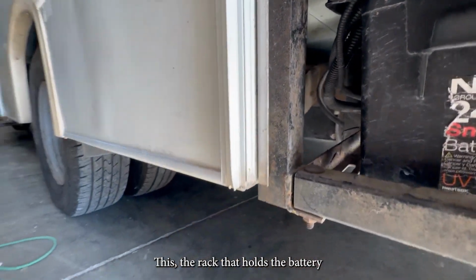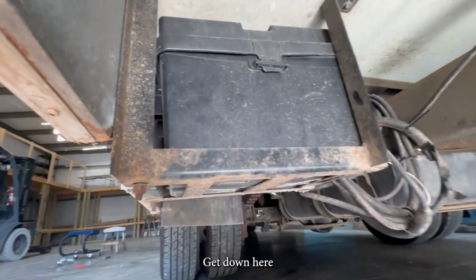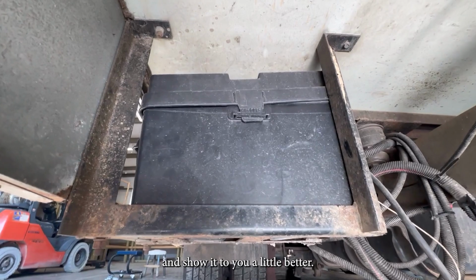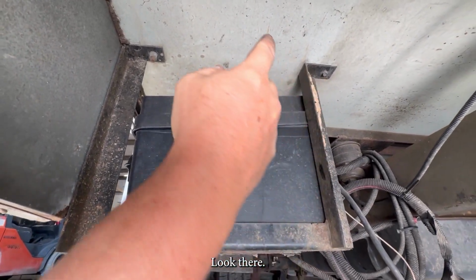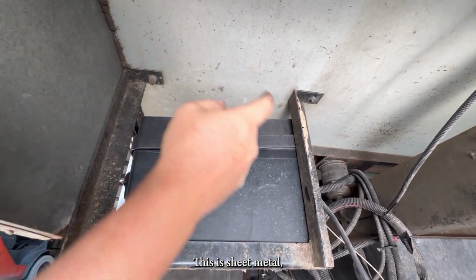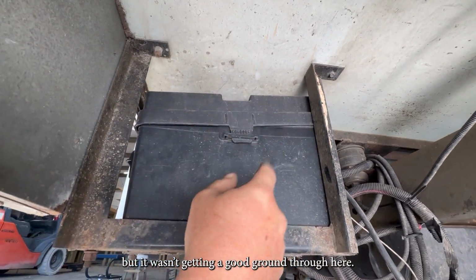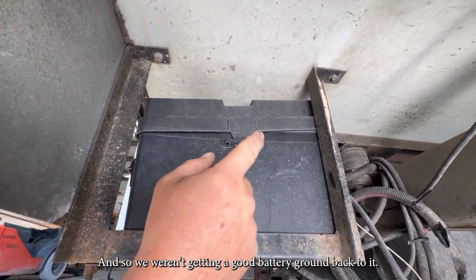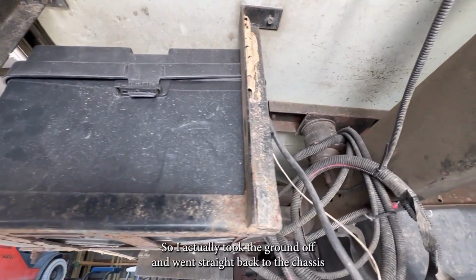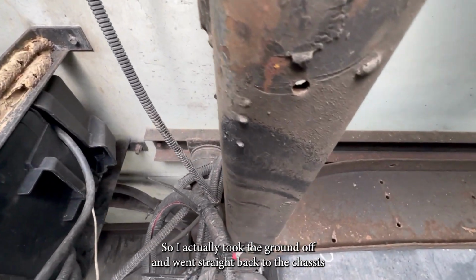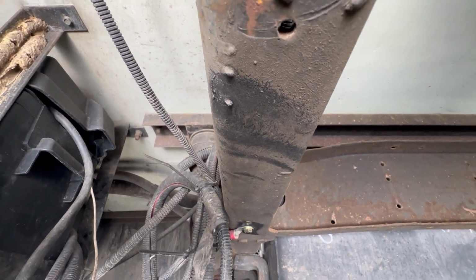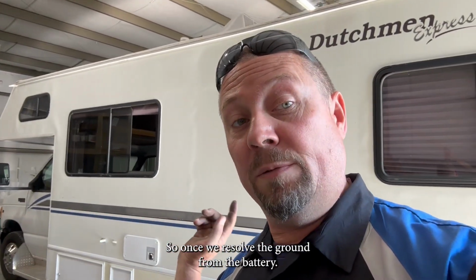What we found out was the rack that holds the battery, let me get out here and show it to you a little better. Look at there. This is sheet metal, but it wasn't getting a good ground through here, and so we weren't getting a good battery ground back to it. So I actually took the ground off and we went straight back to the chassis and tied it in right there. So once we resolved the ground from the battery, the generator now works.